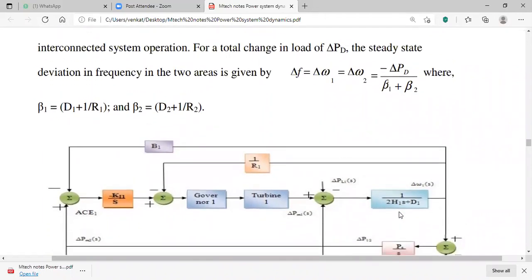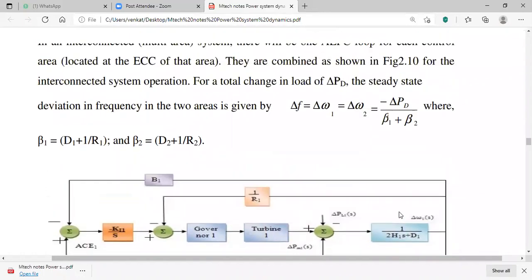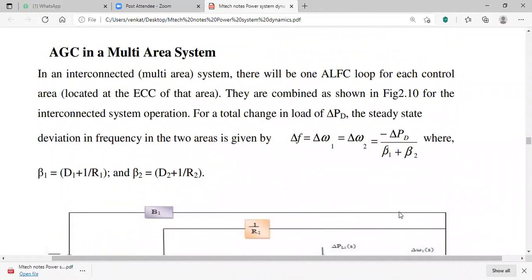In multi-area systems — considering two areas, as shown in the simulation block diagram from the last class — there is one LFC loop for each control area, located at the Energy Control Center (ECC) of that area. They are combined for interconnected system operation. For a total load change delta PD, the steady-state frequency deviation in the two areas is: delta F = delta-omega1 = delta-omega2 = −delta PD / (beta1 + beta2), where beta1 includes D1 and R1, and beta2 includes D2 and R2.